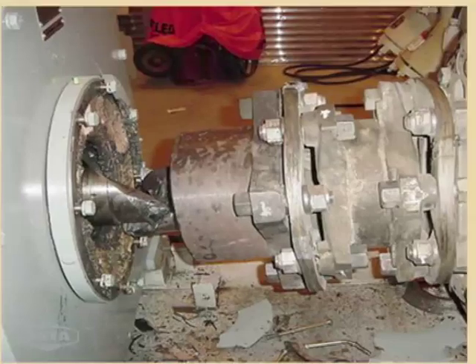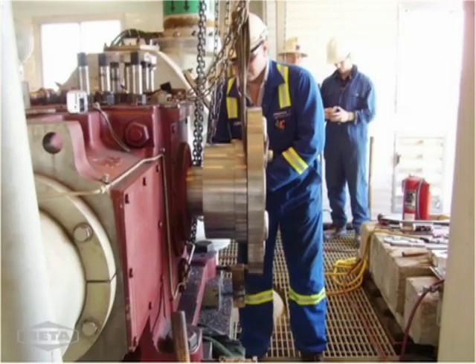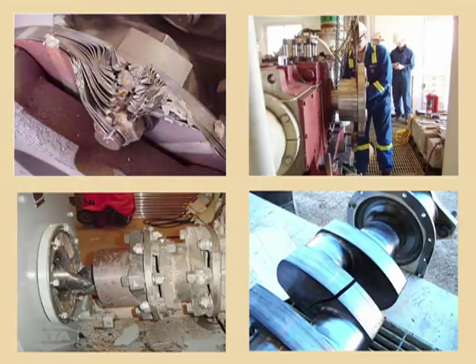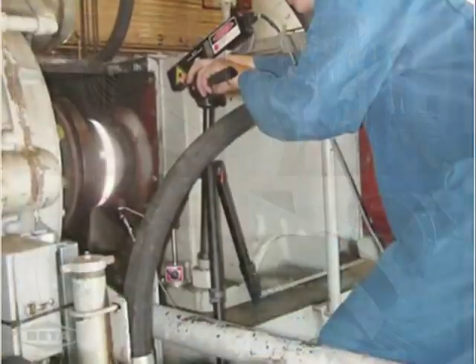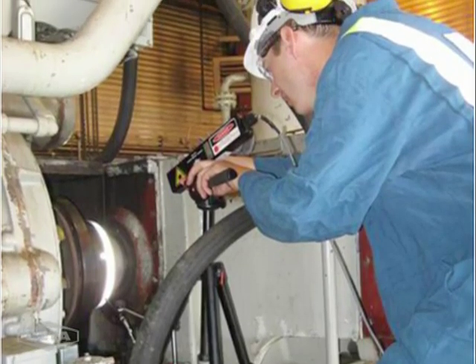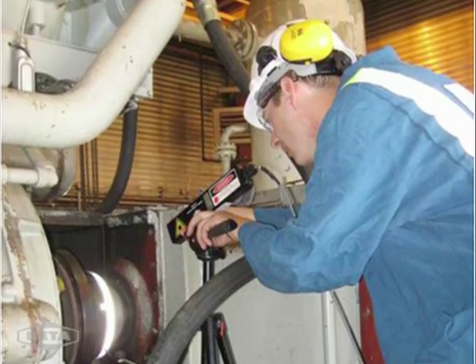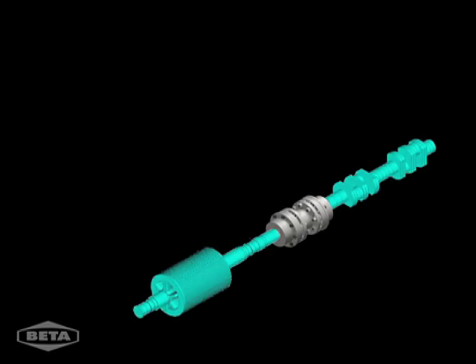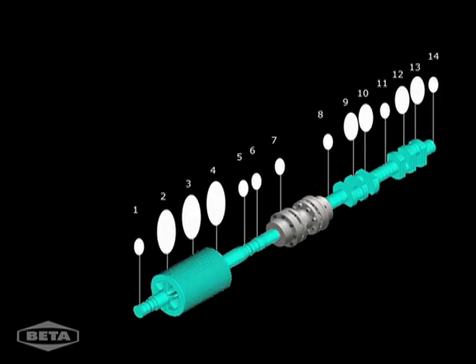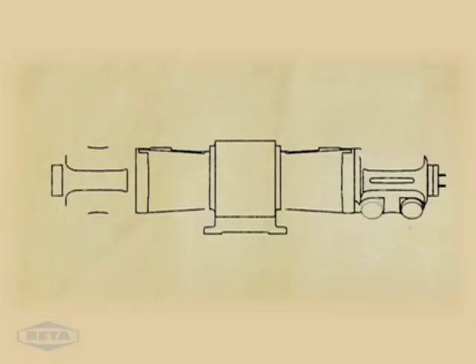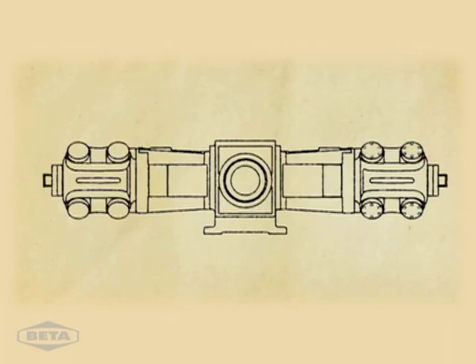Not to mention the downtime and cost if the unit is inoperable for one to two months. Torsional vibration is often called the silent killer because a failure like this occurs without warning. The best way to mitigate these failures is to order a torsional vibration analysis before a unit is built.